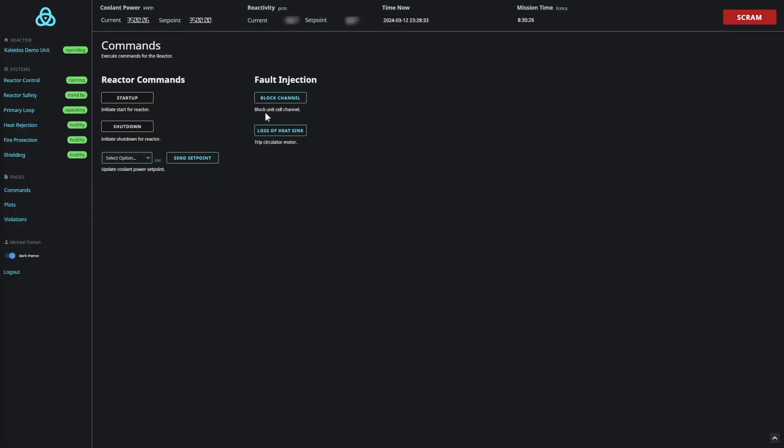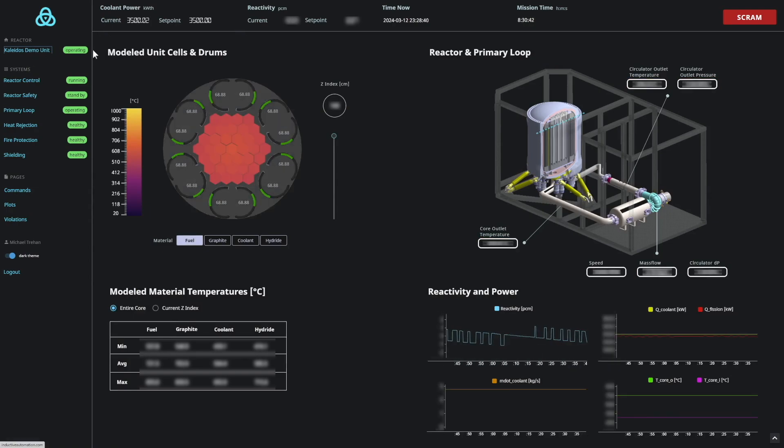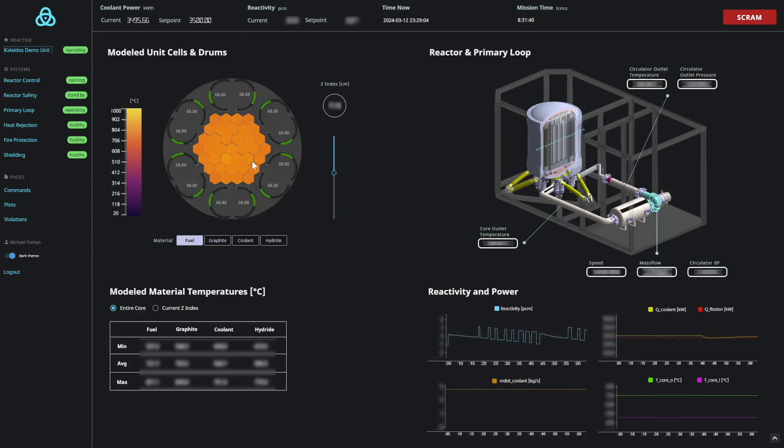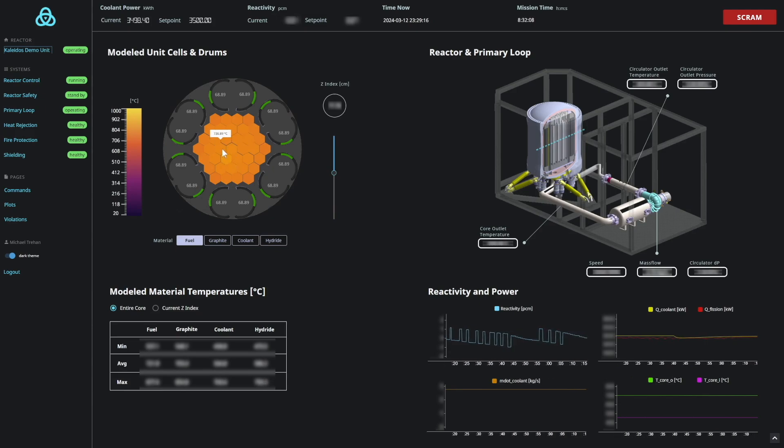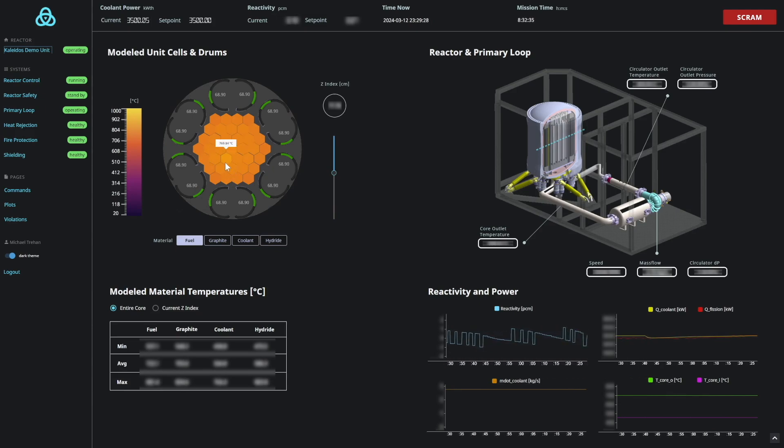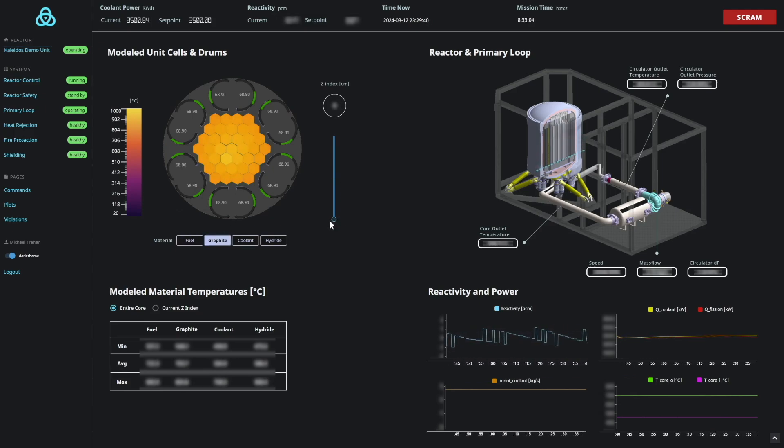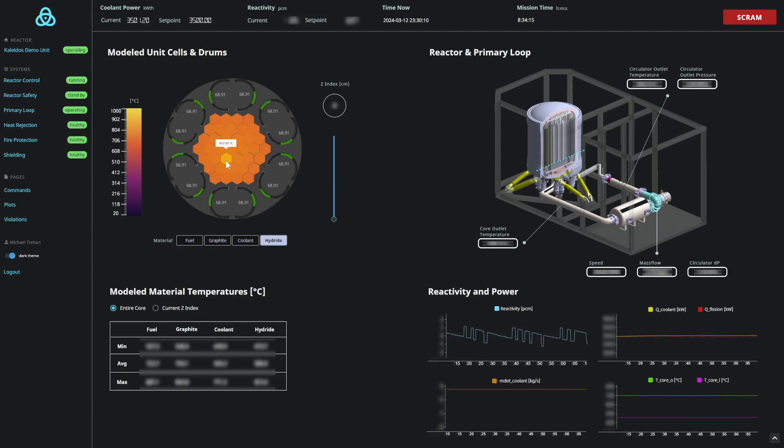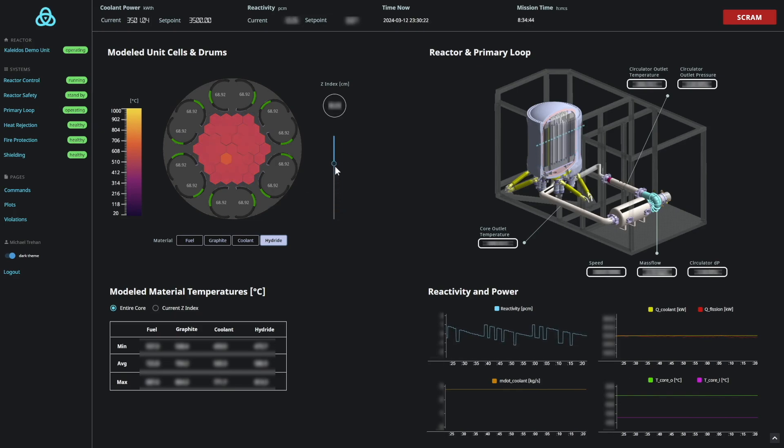Our digital twin technology also enables us to simulate off-nominal scenarios. In this case, we are injecting a failure where a coolant channel's flow is blocked by 50%. As the simulation progresses, the channel with the blocked pathway begins to heat up. Cycling through the different components shows the impact that this has on their temperatures.